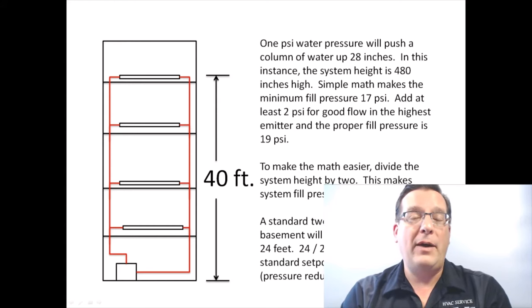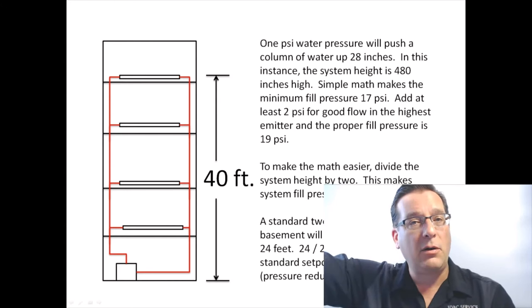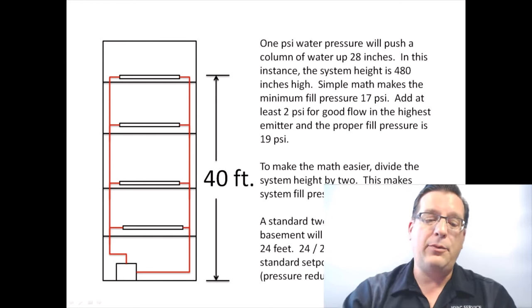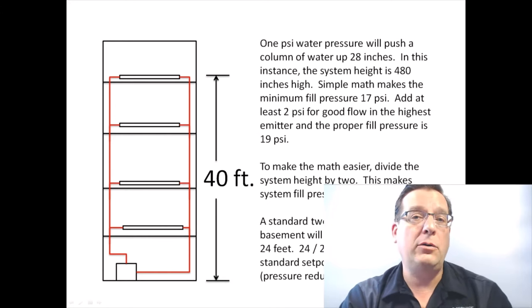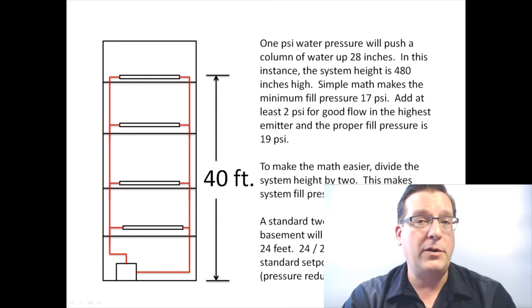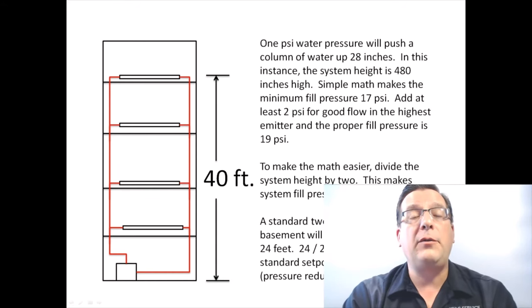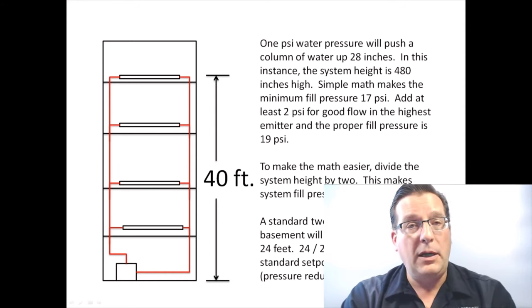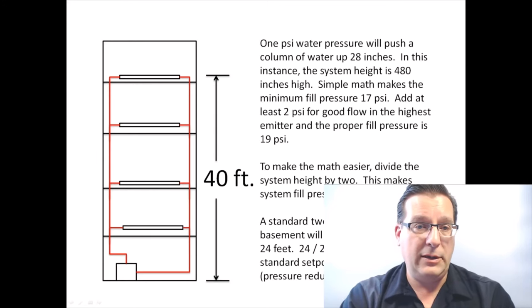So that's the rough idea: take your total system height, divide it by two, and that is a pretty good cold fill pressure. When I say cold fill pressure, I mean when you're filling a boiler for the first time and everything's cold — that's what the pressure should be. It needs to be enough to fill it all the way to the top, plus a little bit extra to make sure the upper regions don't go to zero.